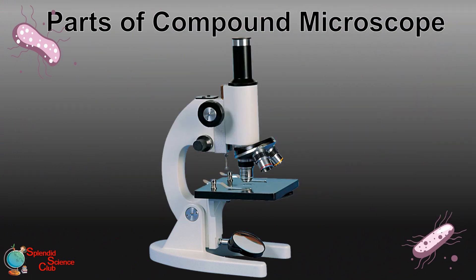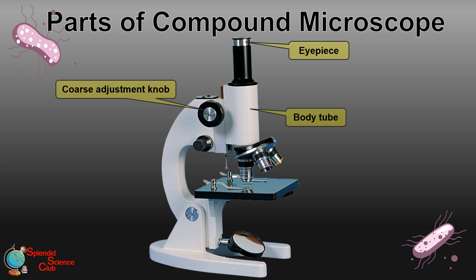Let's identify the main parts of a compound microscope. The eyepiece is on top — you have to keep your eye about one centimeter above the eyepiece to see through it. Below that is the cylindrical body tube, which is moved up and down by the coarse and fine adjustment knobs. The fine adjustment is used for little changes to focus the specimen.